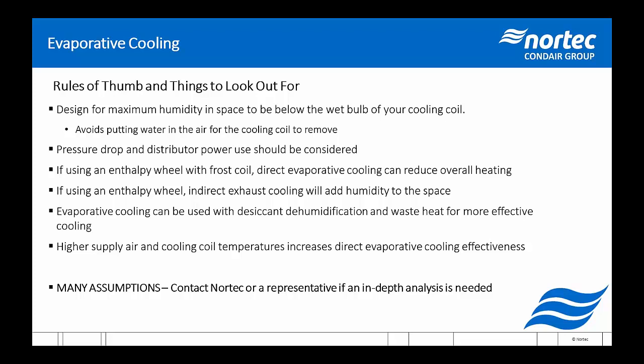Evaporative cooling can be used with desiccant dehumidification as well. So that's if you have a desiccant dehumidifier to dehumidify the air stream coming in, the fresh air. And that can be through waste heat or through solar heat. And you can put an evaporative cooler after that to significantly increase the amount of cooling you'll see in the air. And yes, you have some heating from the desiccant coil, but you'll end up with far more cooling than you see on the heating side. And finally, the higher your supply air and cooling coil temperatures are, the more effective we can be with evaporative cooling in duct. So that would mean if you're able to apply 60-degree air with 58 wet bulb, you have more significant cooling applicability.